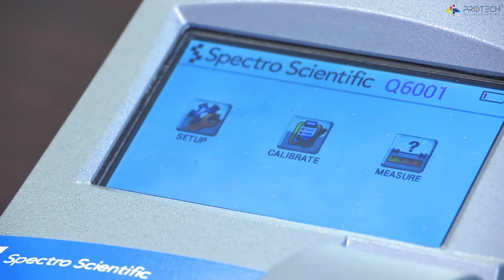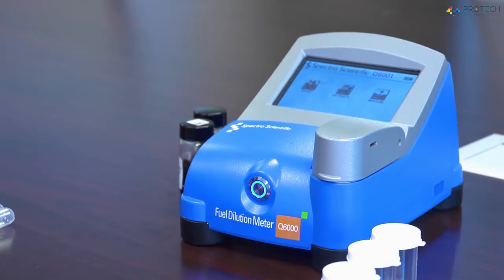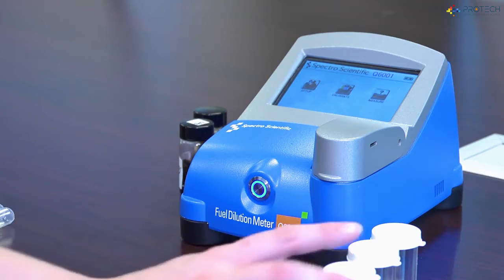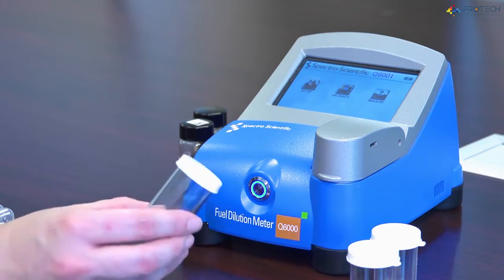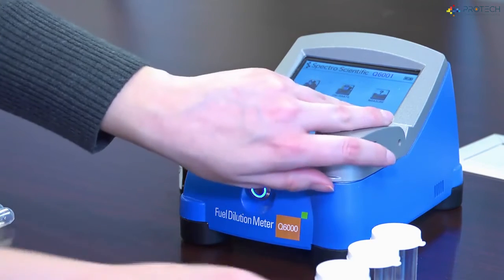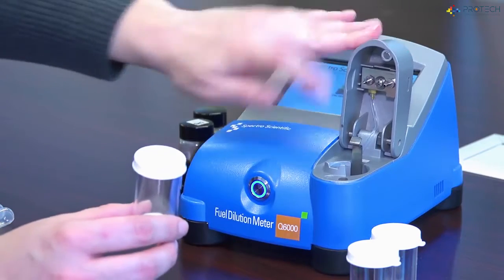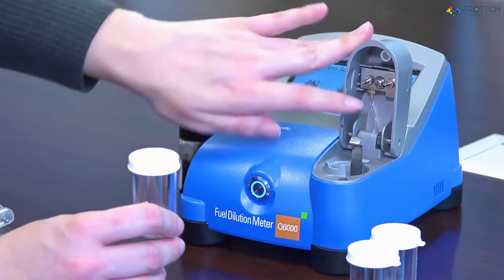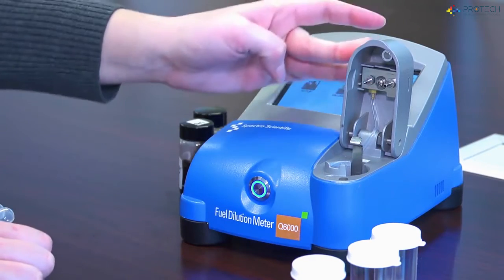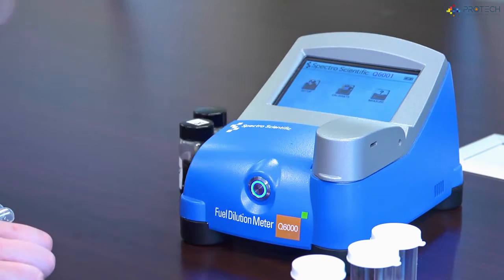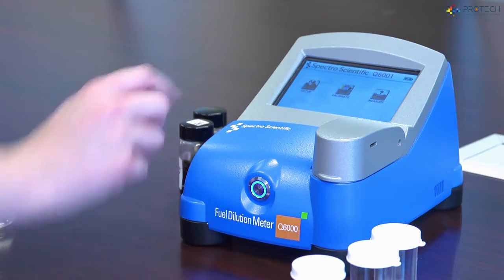So this is the Q6000 fuel dilution meter. The way that it works is it uses a surface acoustic wave sensor to detect the amount of fuel present in the headspace over an oil sample. You have the sample vial, which sits in the sample chamber, and you have fangs which pierce the cap and sample the headspace to determine how much fuel is in the headspace and relate that back to how much fuel was in your sample.